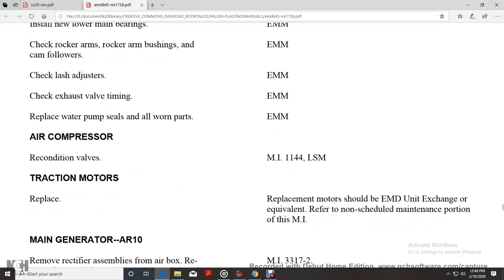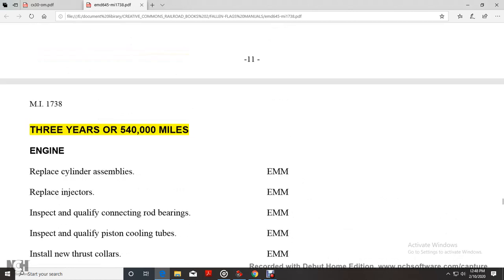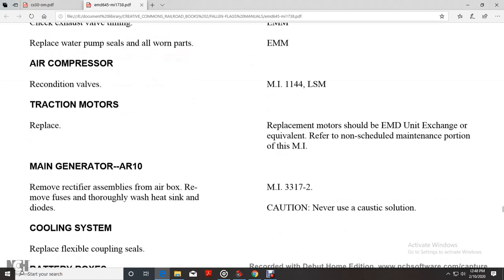Traction motors need to be replaced at 3 years or 540,000 miles. Replace the motors using the electric motor division unit exchange or equivalent for non-scheduled maintenance portion of this maintenance instruction. Main generator AR10. Remove rectifier assemblies from the airbox. Remove fuses. Thoroughly wash heat sink and diodes. Maintenance instruction 33172. Caution: never use a caustic solution.